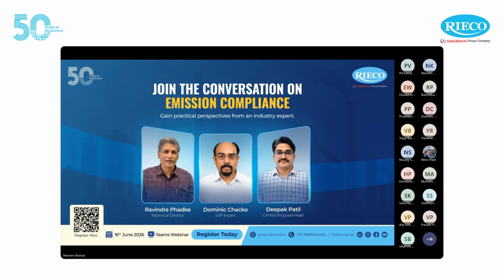But the ESP, because of the large collection area it has, has much more potential to perform better than that. Only this back corona is preventing the ESP from performing better. So this technology has recently become more cutting edge. Technology has improved, and thereby there are better electrical charging methods through which this problem can be addressed. As a general term, that kind of charging is called HV pulsing, high voltage pulsing.